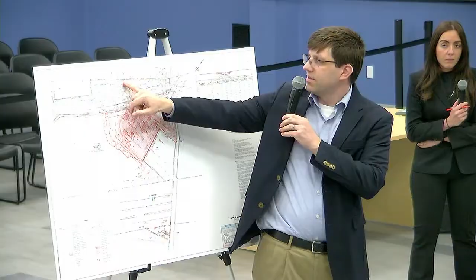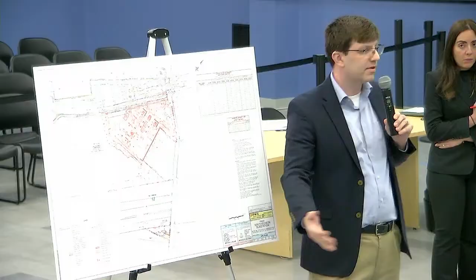Does that make a difference? No, we don't have a lot of. So trees don't block sound for the most part. So if you have hundreds of feet of dense woods, that may matter. But what we're talking about here is we're going to come over to this fence line just on this side of the creek and measure noise from the whole site. And we're going to get all the fans turned on here and all the fans turned on here. When we do that, even if it's winter, we'll run the fans to simulate summer conditions.